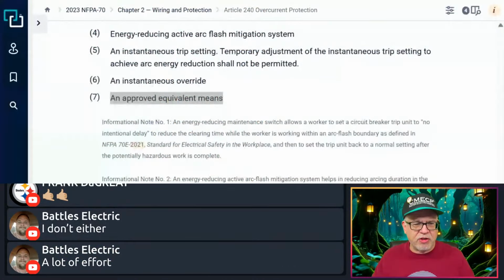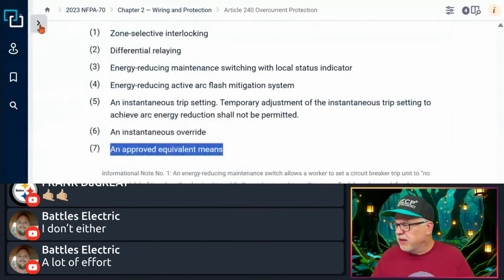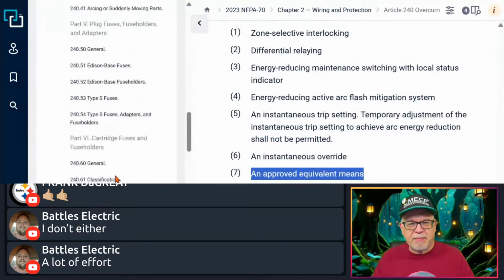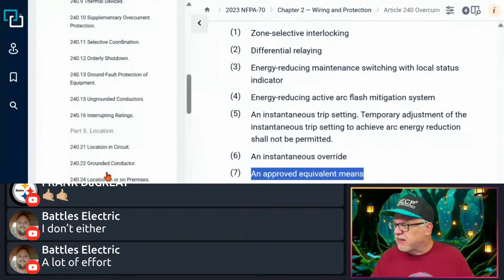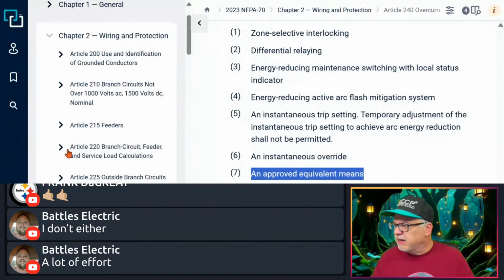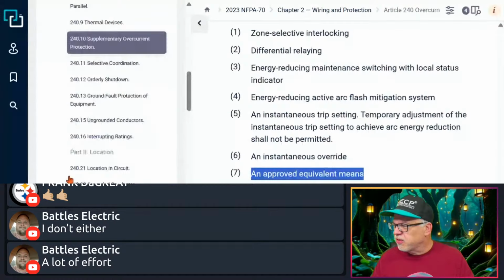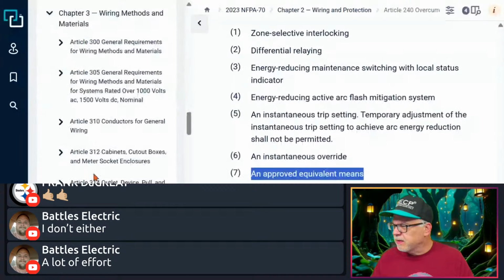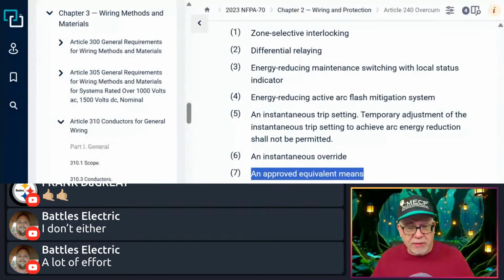Okay, so we'll go look at the NEC, and then we're going to answer your question, Brandon, if you hung in there for me. All right, so the first thing I want to look at is the ampacity of the conductors, right? So first things first, I'm going to go to 310.16 really quick. And again, we're going to assume all terminations, it's THHN, THWN-2. We're going to assume all terminations are rated 75 degrees C. Everything's rated 75 degrees. Most all the breakers are going to be, all the lugs are going to be. That's most common today. So I'm using THHN, THWN-2.